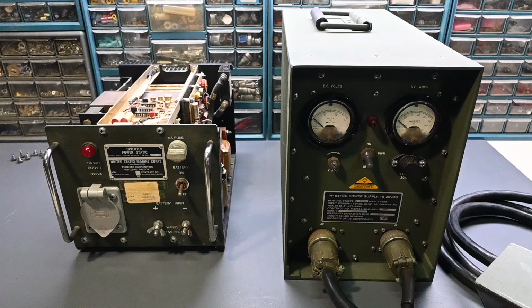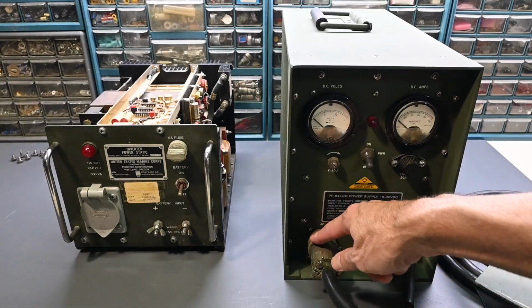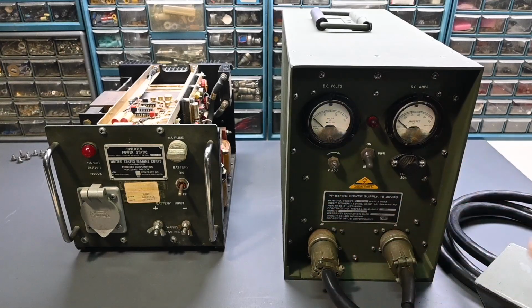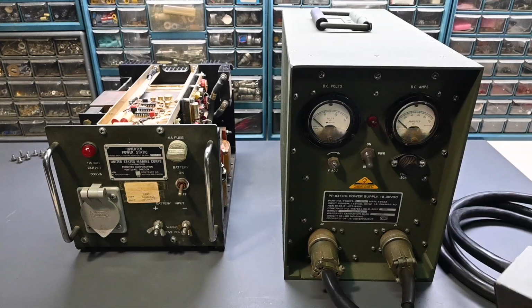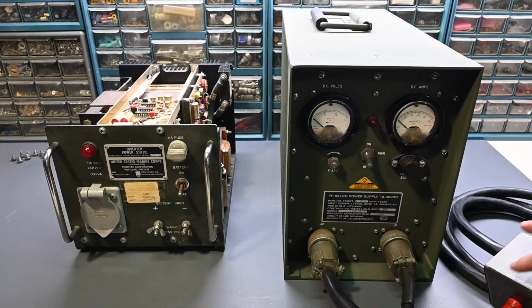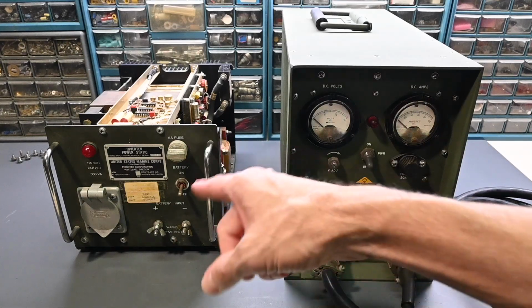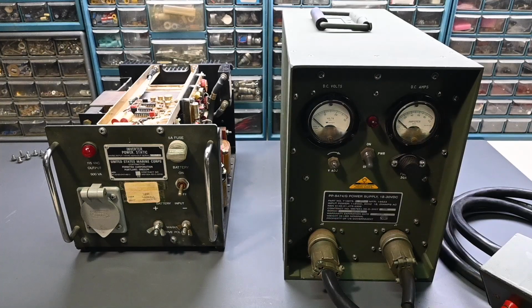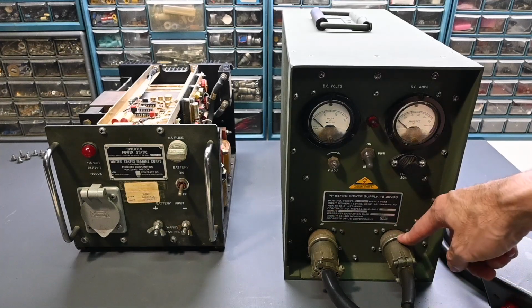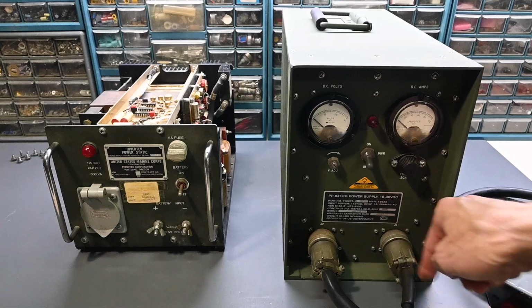Now the output cable is right here - there's a Canon plug or circular connector right here, but this large cable comes over and just goes to this junction box, and there's two terminals on that junction box. So let me get some wire between that junction box and the input terminals on the inverter, and this other connector right here on the power supply is 120 volt input power.